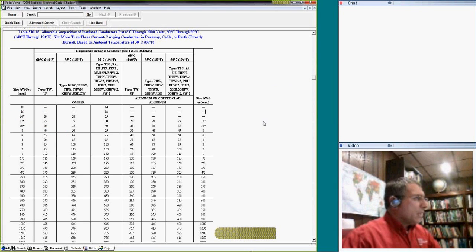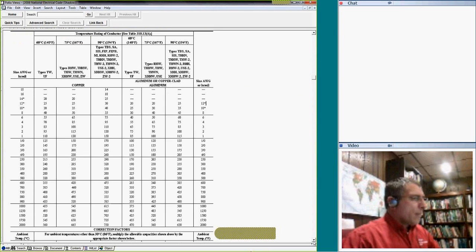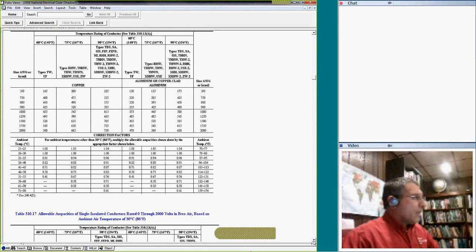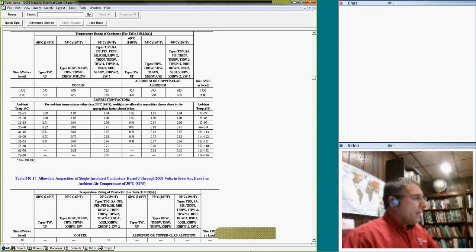So these conductors, guys, no matter what you come up with, are limited by code to 15 amps, this one to 20 amps, and the third one to 30 amps. So no matter what your calculation came up with, use the small conductor rule only for these three conductors. You have to stick with 15, 20, 30. There's some option with motors, but that's the small conductor rule. Now, correction factors, and then I'll let you go.